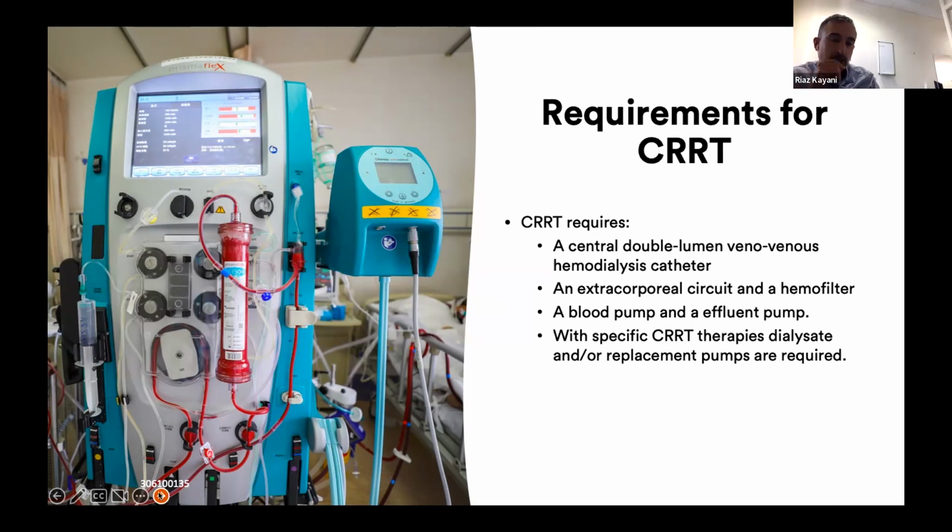That's the basic concept. And you can see slightly in the picture there that there's a cannula there, blood's coming out, and there's a red and a blue. That's just there for simplicity. The blood is going through some plastic tubing, it's going through a pump, it's going through a filter. The thing on the side that you see there is a warmer, and as you can see there, it needs large bore cannulas, and it requires a large amount of circulating blood that goes through the circuit. And you can see the pump there as well.